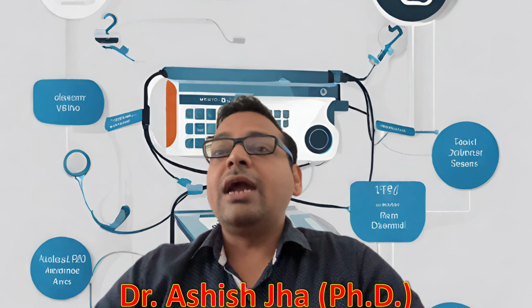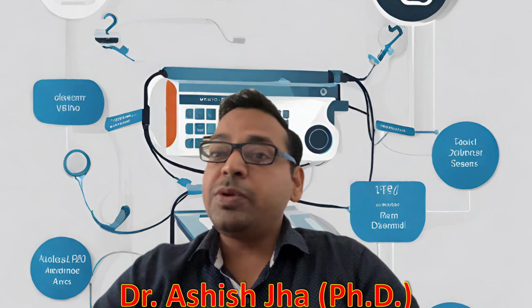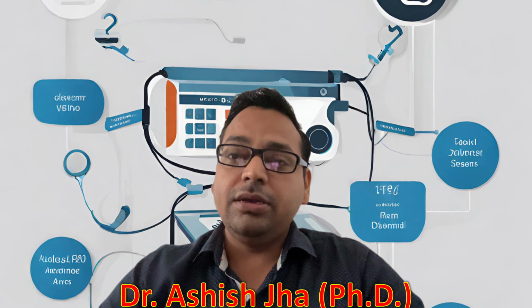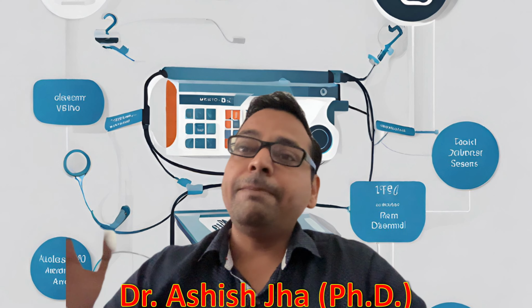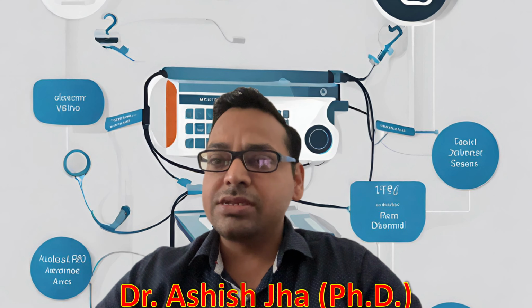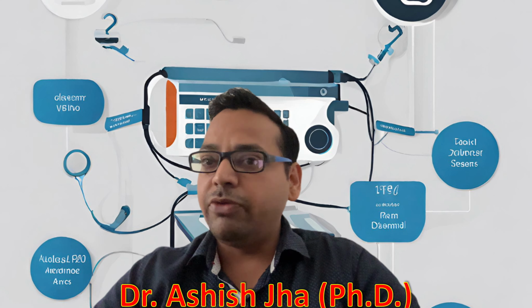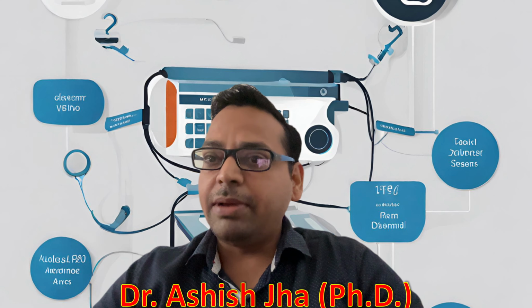And apart from that, when the various technical documentations are submitted by the manufacturer to the regulatory or notified bodies, they specify this particular basic UDI-DI in a specific technical document, so they can trace back those things. They can also easily understand. So technical documentation also has the basic UDI-DI number. We also understand that it's a very unique number for any particular medical device given by the manufacturers, regulated by the EUMDR.